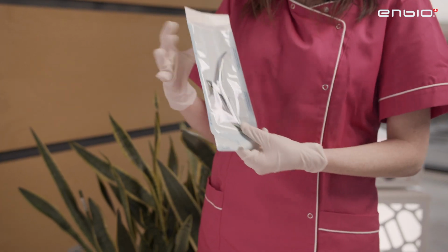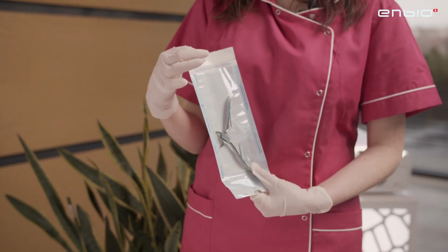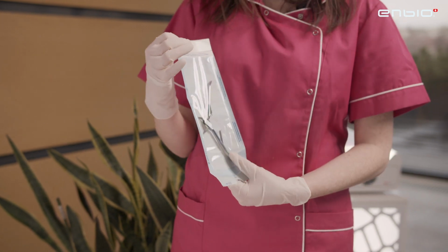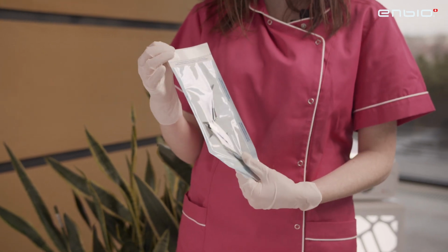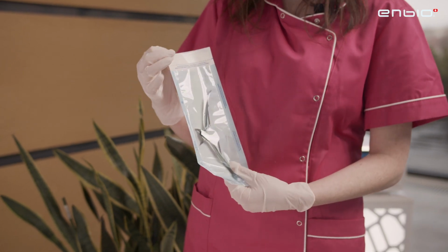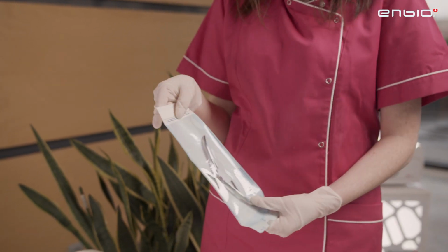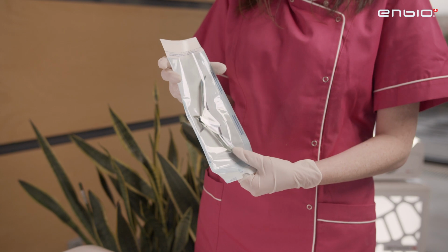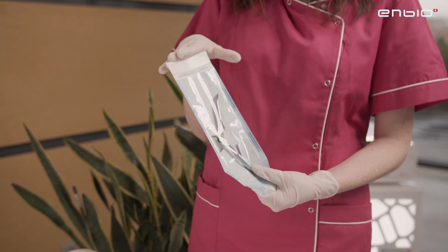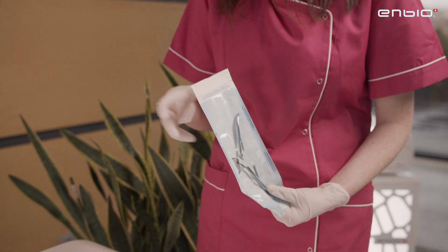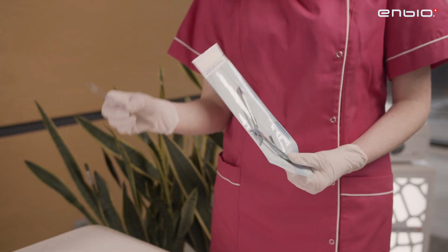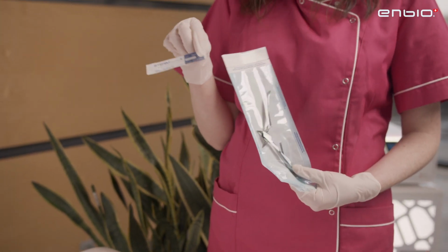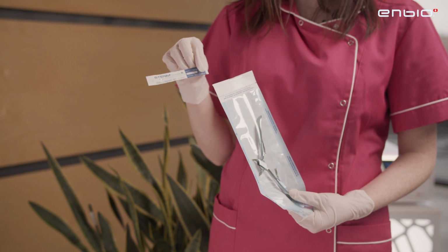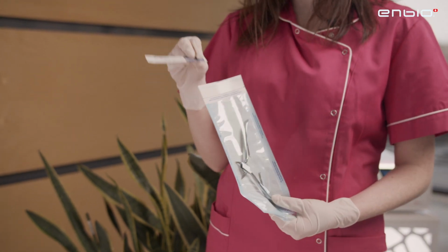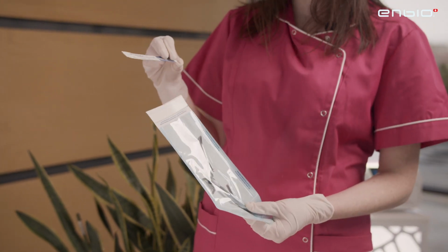After we put the tool inside, it is also important to use a chemical indicator that proves the efficiency of the sterilization process. So for instance, if we are using multiple sterilization pouches, it is enough to put the indicator only inside one of them. And we recommend always to use chemical indicators of class 5 or 6, because these ones are the best, and I will talk about them a little bit later.